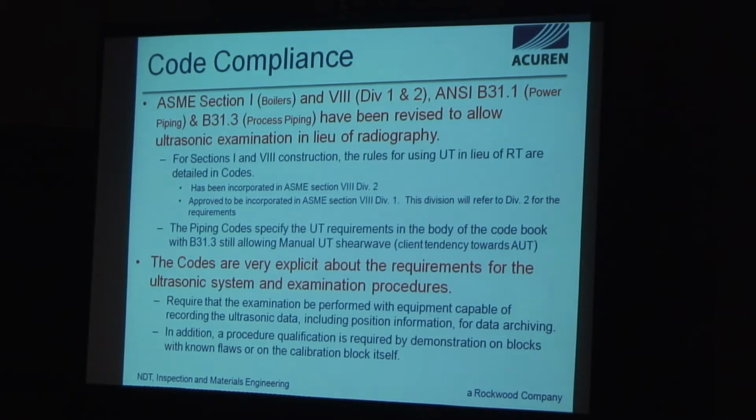The codes are very explicit about the requirements. Of course, the requirement for particular equipment, that is storing data, being able to store data in its raw format such that it can be interpreted by third parties, but also the procedure qualification process. And in my opinion, right now it's just too tedious. Been able to maximize efficiency by building a stockpile of mock-ups and qualification blocks, and over time that gets easier and easier. But it is my hope that one day we'll truly be able to do these kind of qualifications with beam tool programs and analytical modeling, rather than actually building these blocks and doing it out there in the field.